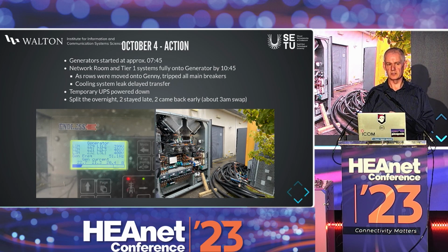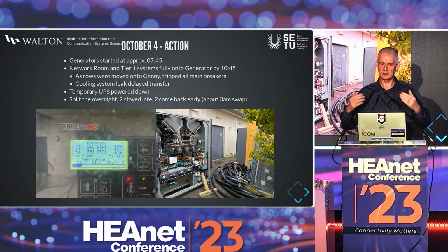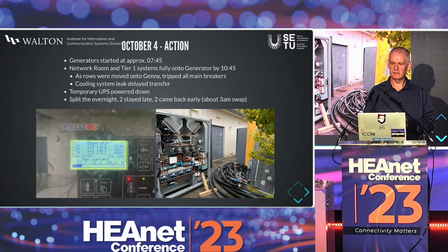Engineers wanted to do some maintenance. When we said shut down to them, we meant the IT was shut down, not the cooling system. Someone opened a valve and proceeded to blow water under pressure out of a 2-inch pipe around the place, which we really didn't need. That was our fault, and it powered down the temporary UPS system.